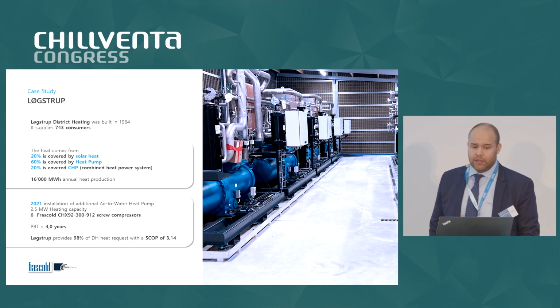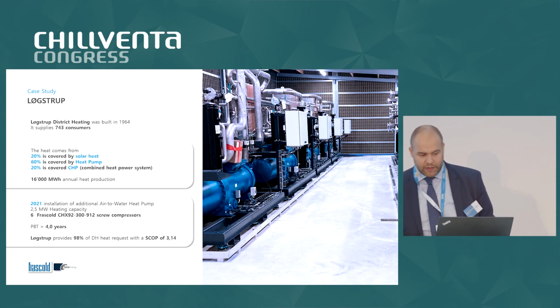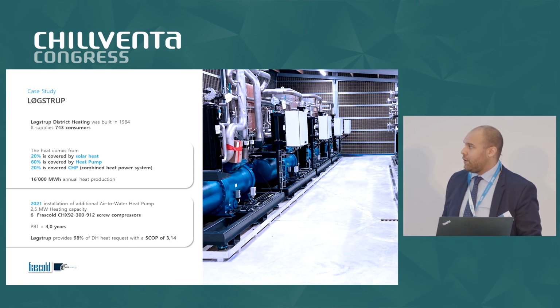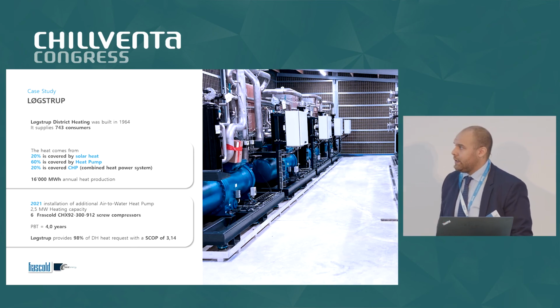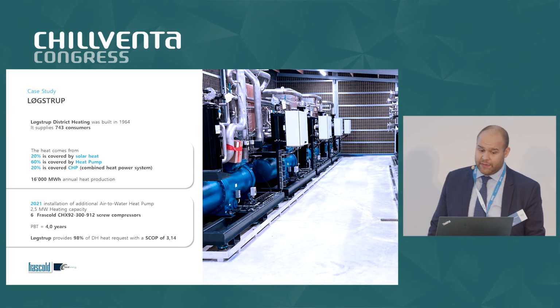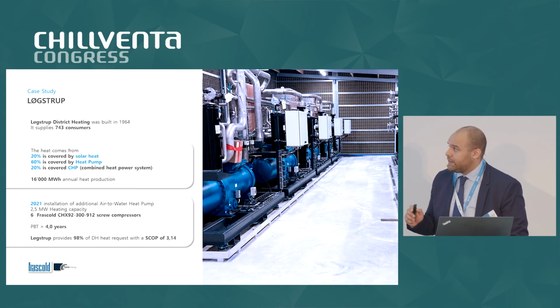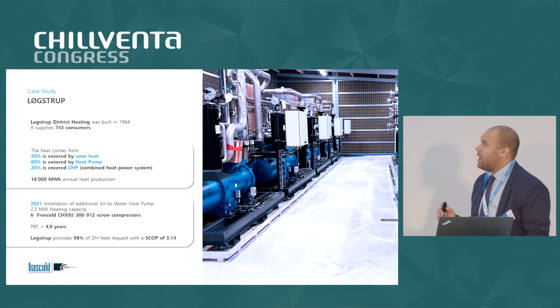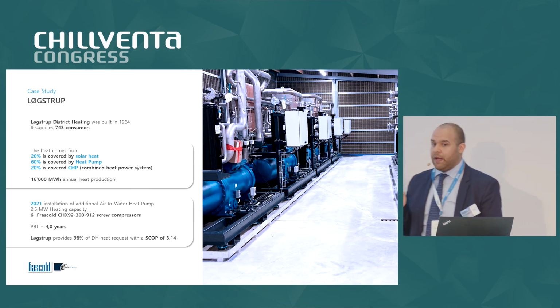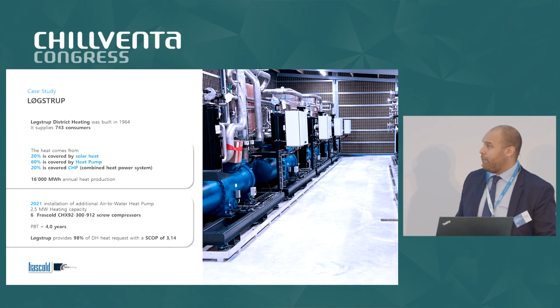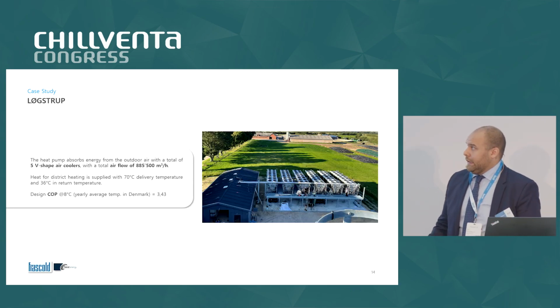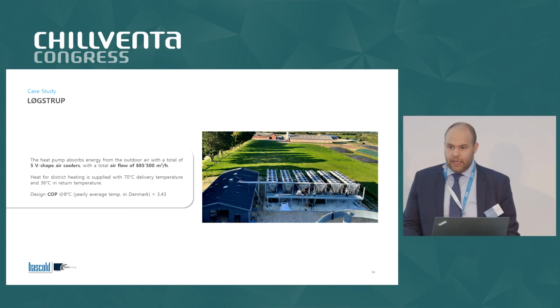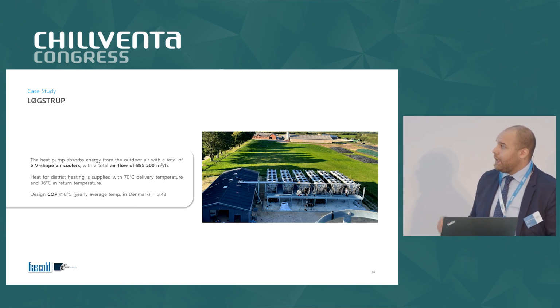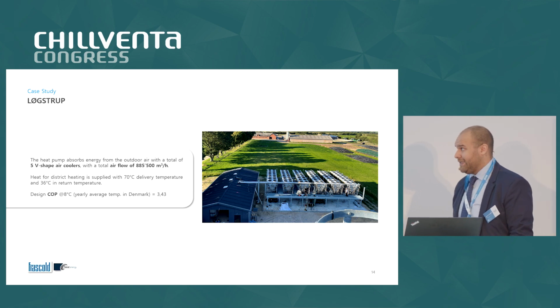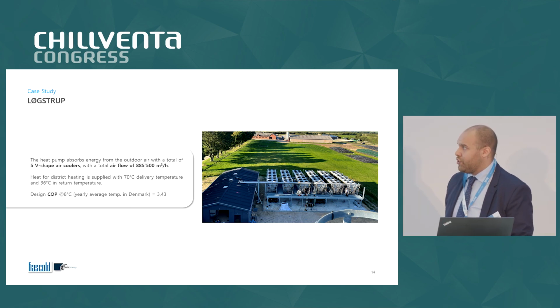In 2021, there was an installation of an air-to-water heat pump that covered 2.5 megawatt of heating capacity using 6 CHX Frascold compressors. The payback time for this system was 4 years. Also in this case, the COP is above 3, in this case 3.14. The delivery water is 60, like the case before, and the design COP at 8 Celsius of ambient temperature, the yearly average in Denmark, is 3.43.